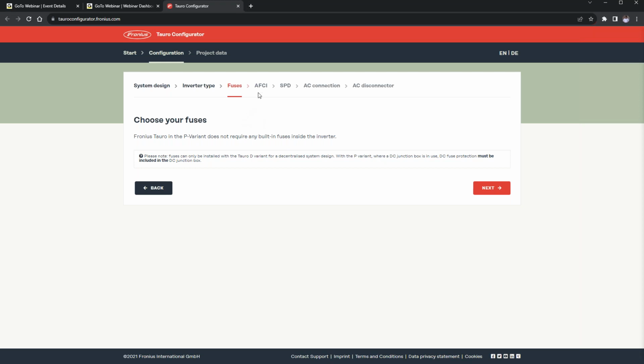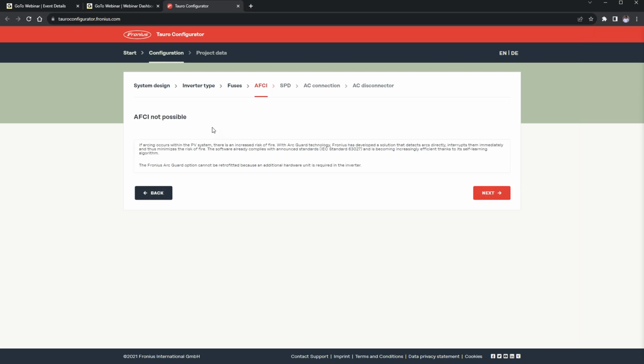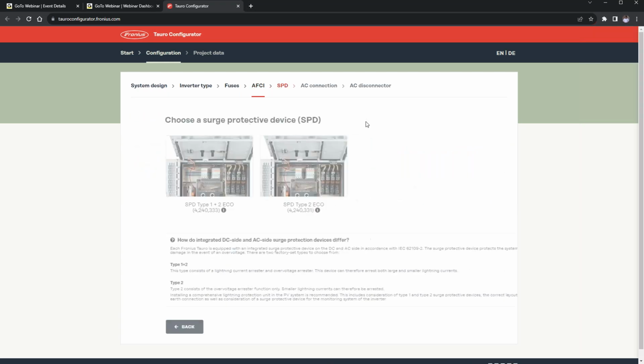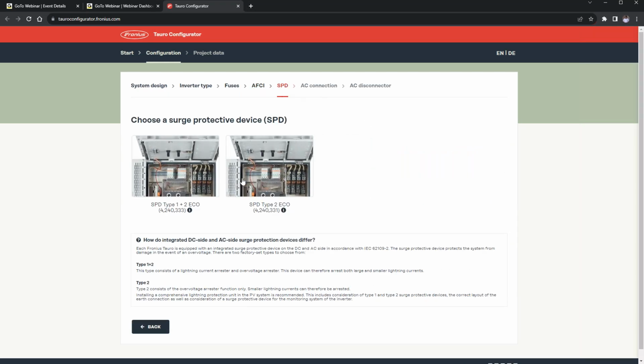So next up is the AFCI, which in this case also is not possible because of the nature of the cabling, because you're coming with bigger diameter cables, so this would not be implemented for AFCI. Next up is the surge protection. So for surge protection device, you would now have to select between type 1+2 or type 2. Type 1+2 gives you protection against lightning current and overvoltage, okay? While type 2 gives you protection over just overvoltage alone.